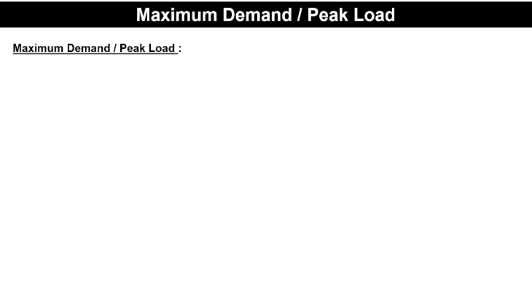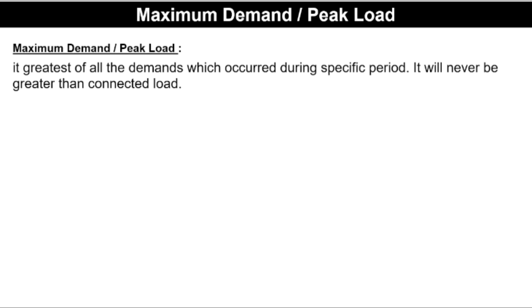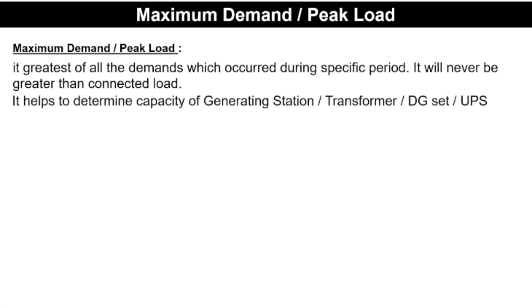What does maximum demand or peak demand mean? We know if the connected load of a house is 10 kW, all 10 kW will not operate at the same time. Sometimes 2 kW will operate, sometimes 5 kW, and sometimes 3 kW. The operating load at a time is varying and is never greater than the connected load. The maximum load which operates during a given time is called the maximum demand or peak load — it is the greatest of all demands occurring during a specified period and will never be greater than the connected load. It helps in determining the capacity of a generator, DG set, and UPS.